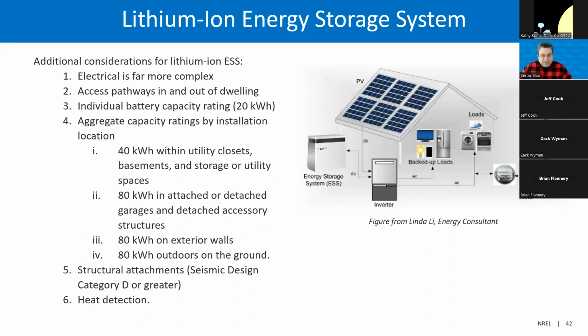The aggregate capacity rating for the energy storage system installed within utility closets, basements, and storage or utility spaces should be 40 kilowatt-hours. In attached or detached garages, detached accessory structures, exterior walls, and outdoors on the ground, it should be 80 kilowatt-hours. The inspector must check access pathways in and out of dwellings and verify that the structure attachments follow the seismic design requirements of their category. For example, much of California is in seismic design category D or greater, which requires the most robust structural design consideration.